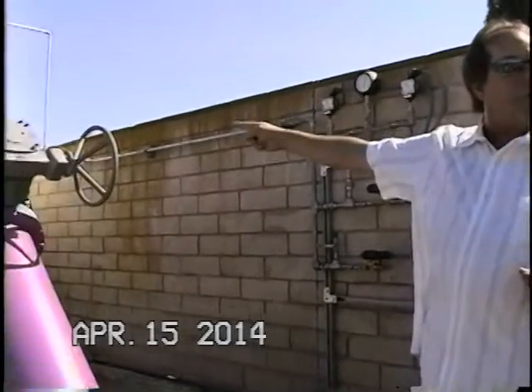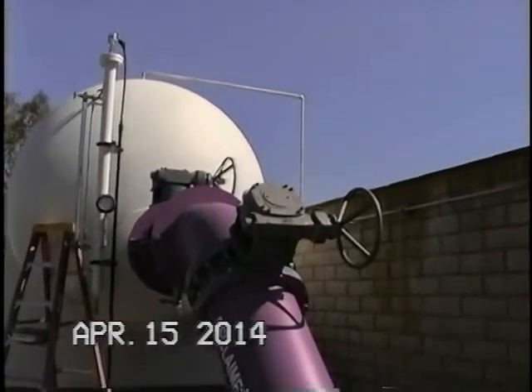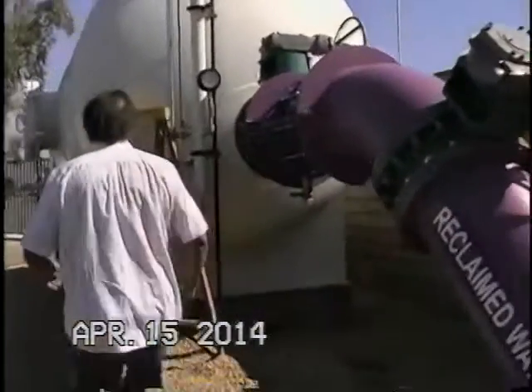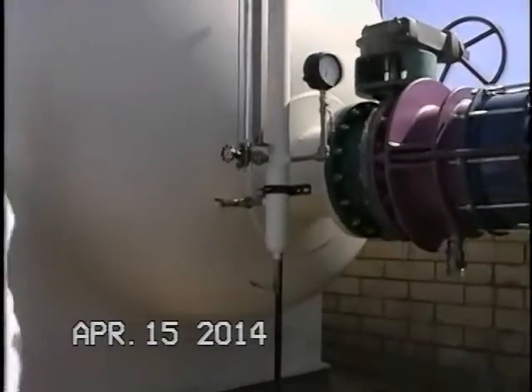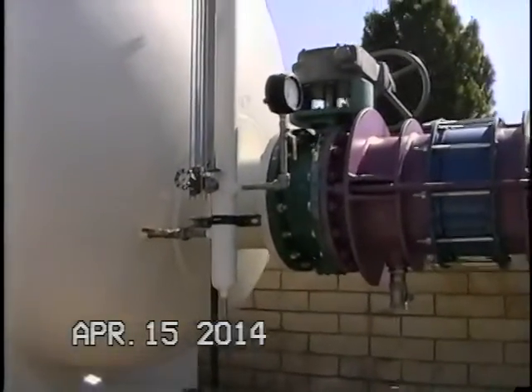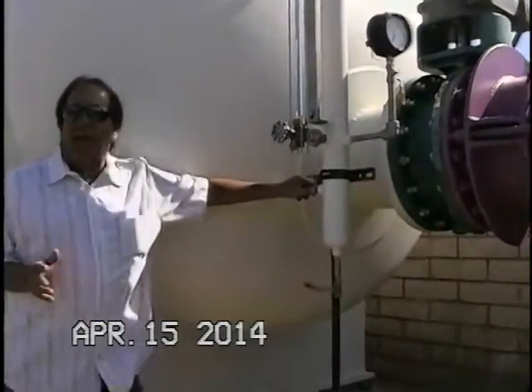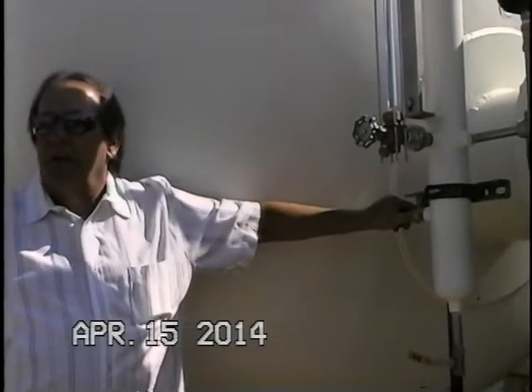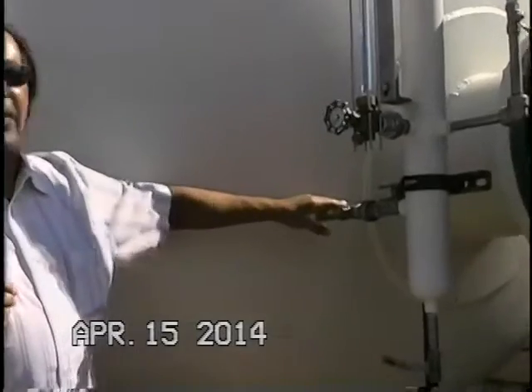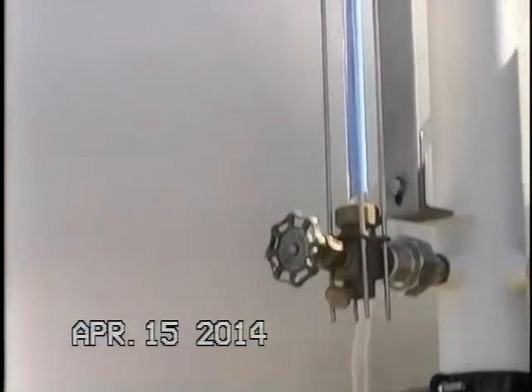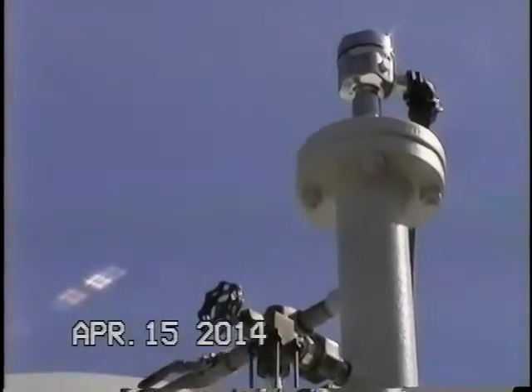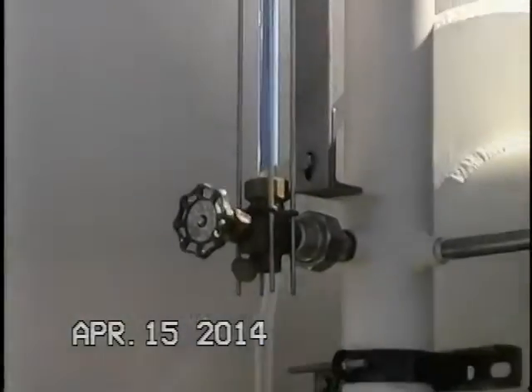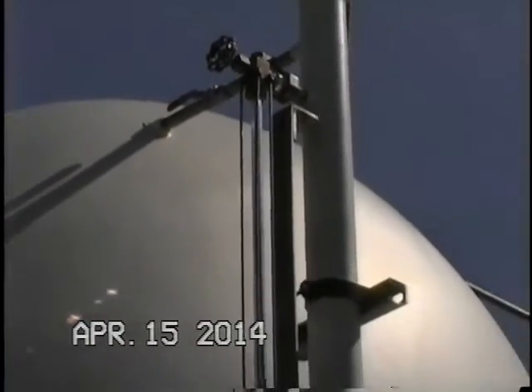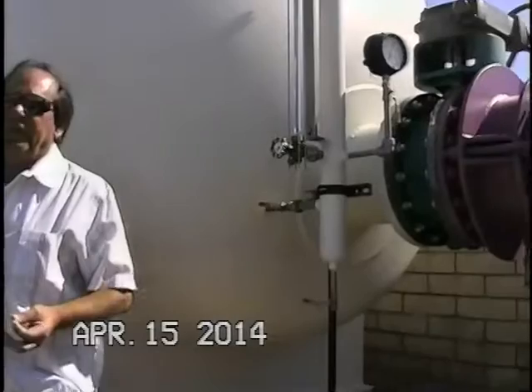The nice thing is you can test this system by isolating the two inlet outlets of the probe well. And maybe we should move over and reposition so I can go over this. This is important. This stilling well gives you the ability to test the system without interrupting the process and keeping the tank online. One of the things that you can do, we have these isolation valves. You can shut the top one off, the bottom one off, and then you can drain the probe well completely out of air and water. That allows you to leave that top valve closed, open this bottom valve, and you can fill the probe well to whatever desired level that you want.